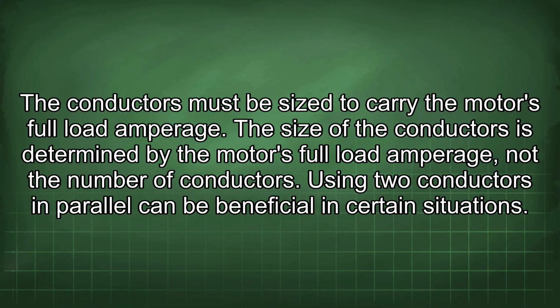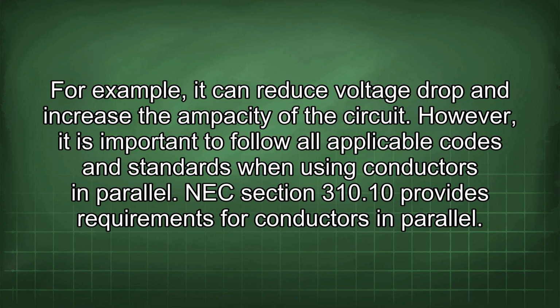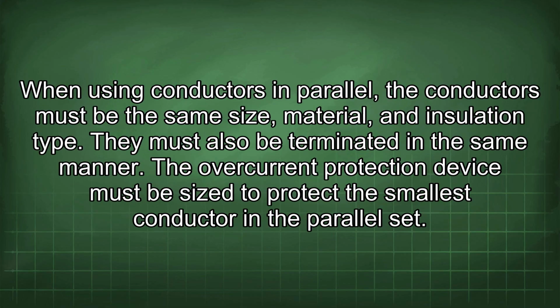Using two conductors in parallel can be beneficial in certain situations. For example, it can reduce voltage drop and increase the ampacity of the circuit. However, it is important to follow all applicable codes and standards when using conductors in parallel. NEC Section 310.10 provides requirements for conductors in parallel. When using conductors in parallel, the conductors must be the same size, material, and insulation type. They must also be terminated in the same manner. The overcurrent protection device must be sized to protect the smallest conductor in the parallel set.